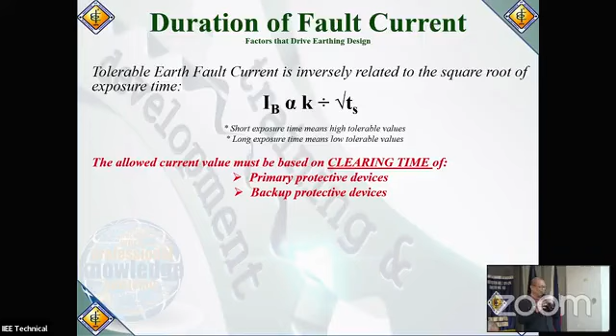Primary protection clearing time is possible due to low combined probability. Ibig sabihin, baka isa na lang ang i-consider mo kasi ang probability of two failing ay mas mababa, lalo na sa simpler systems. Pero sa HV, 69 kV and above, or 36 kV and above, dinodoble na namin yan - meron kang backup protection.